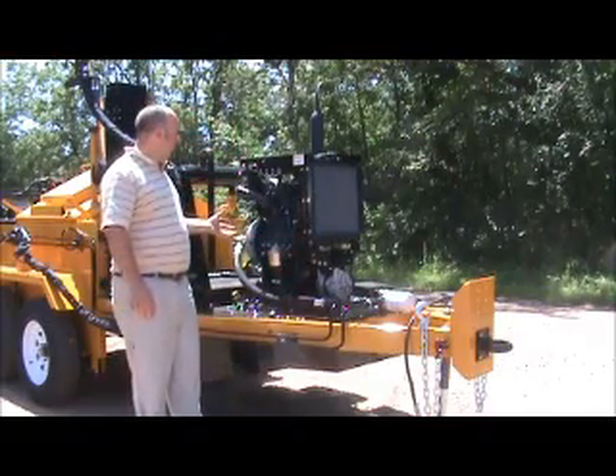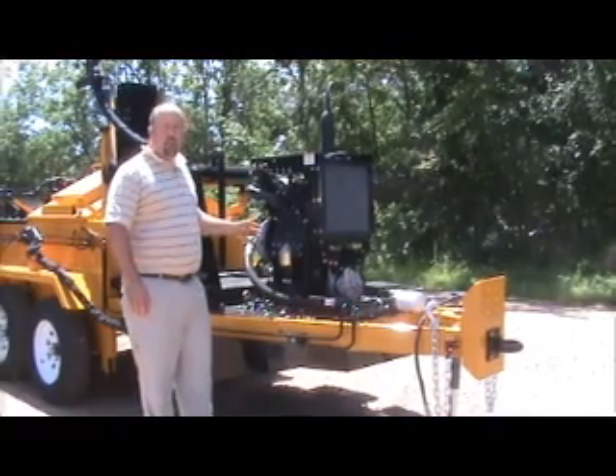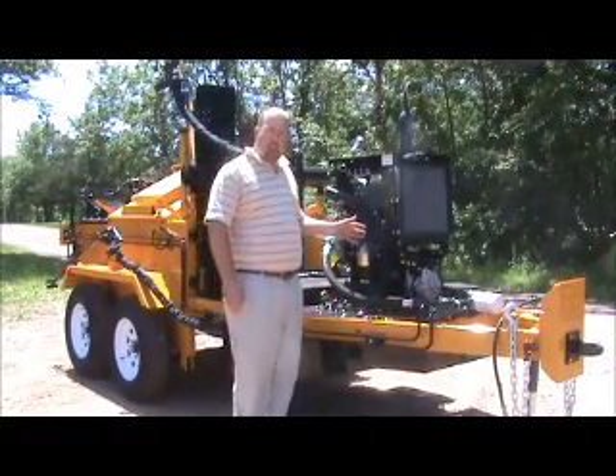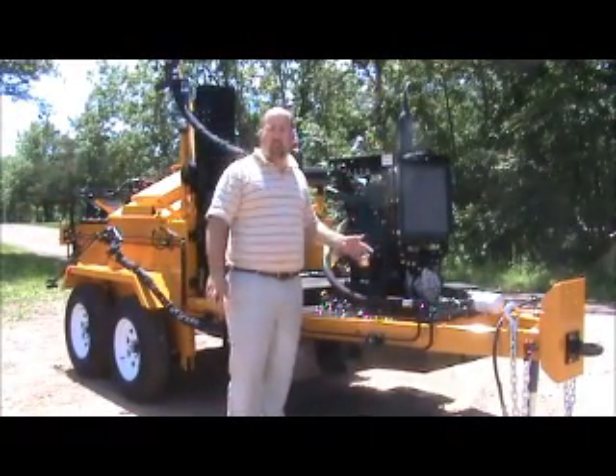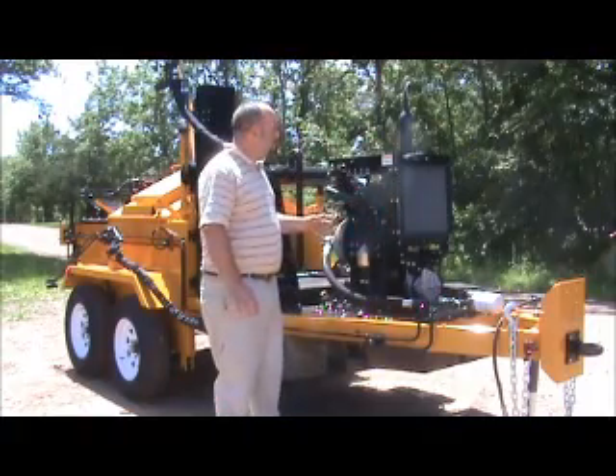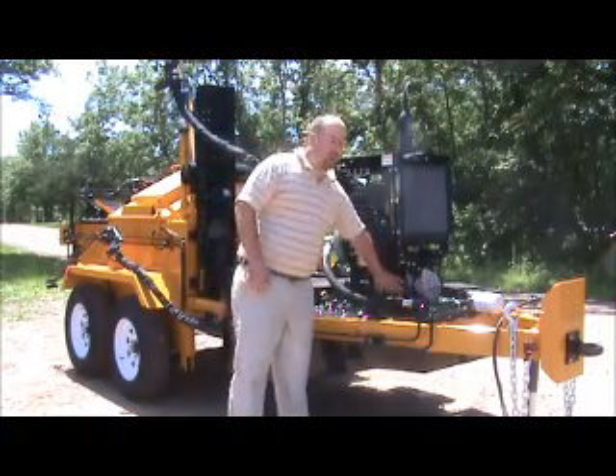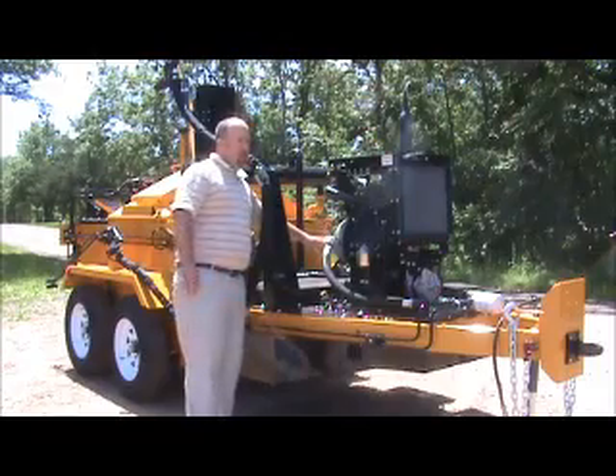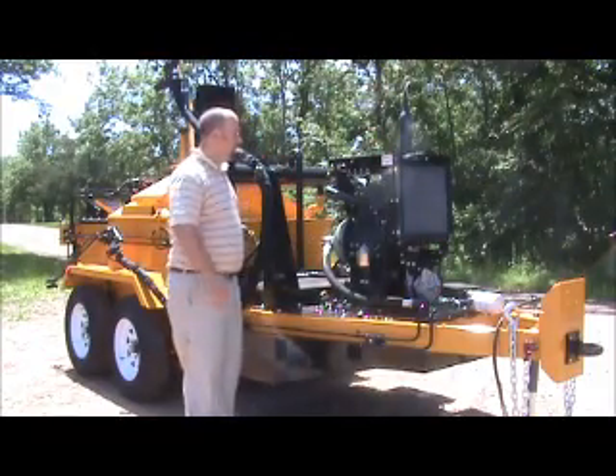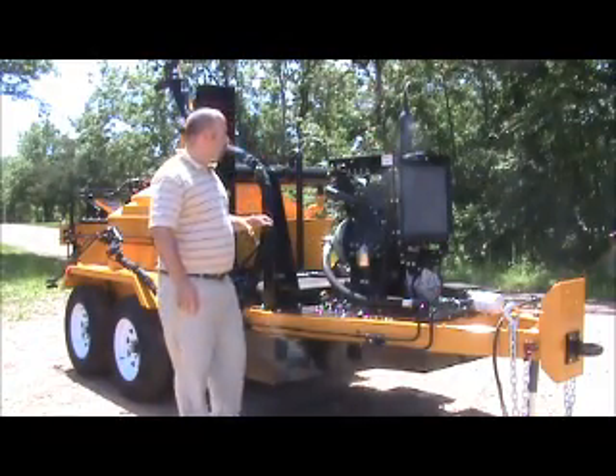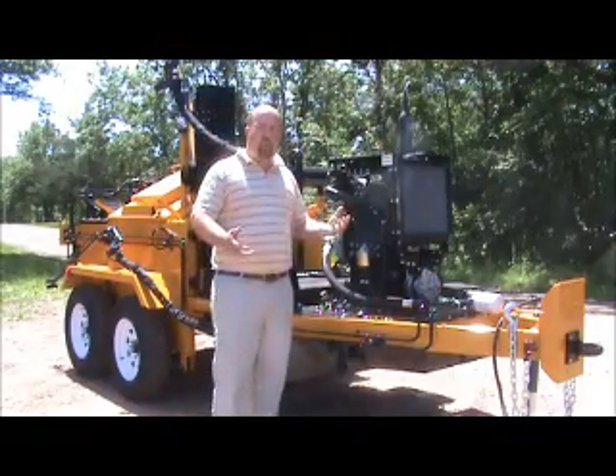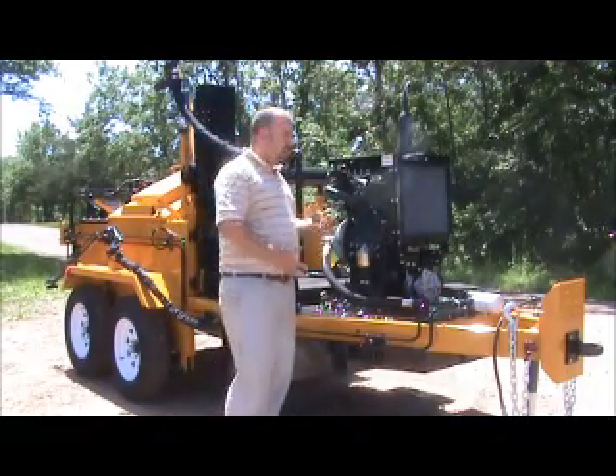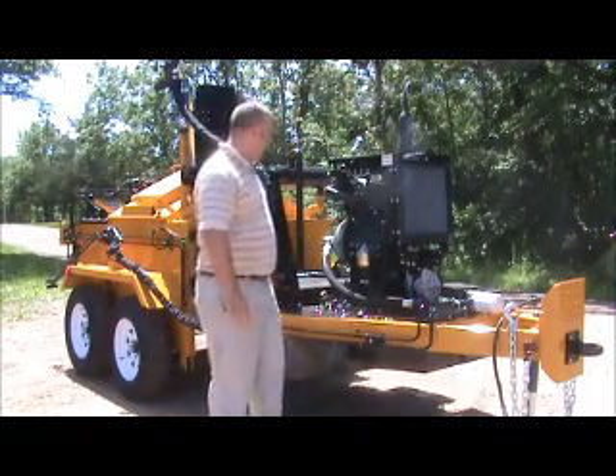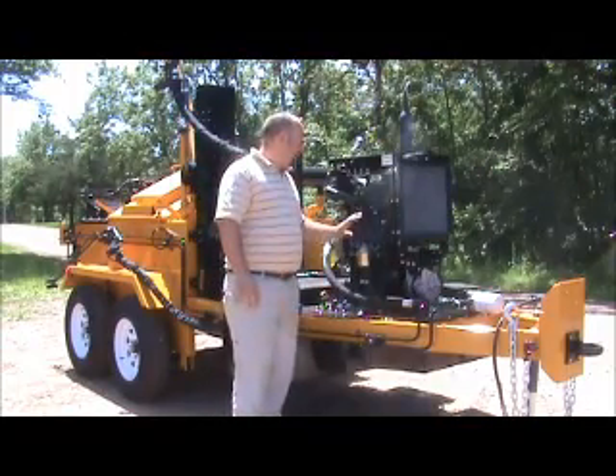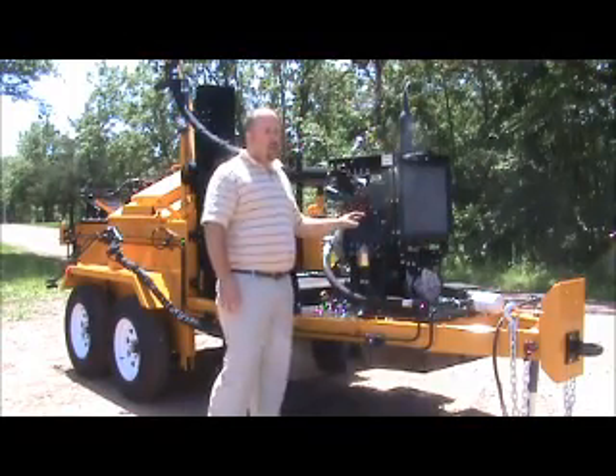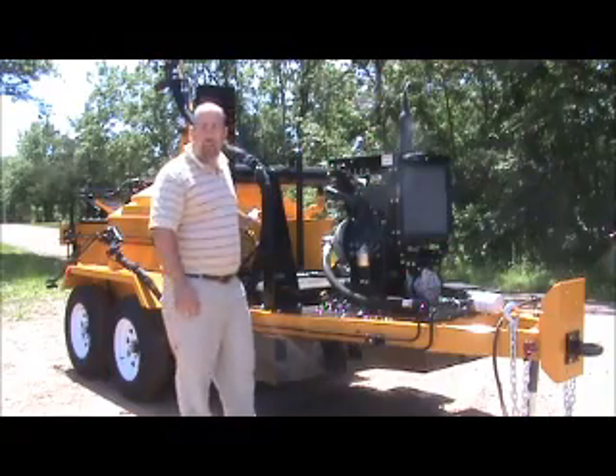The engine itself has a governor. There's no throttle, so you're going to start the engine, it's going to come up to speed. It's going to be set at the right engine RPM so that you have enough power to run the alternator and also the hydraulic system and the other 12-volt alternator on the other side. It's very important on this unit that we have the engine running, and we'll go over that in some of the heating system portions of it. One of the things that the hydraulic system runs on here is actually a hot oil circulating pump.